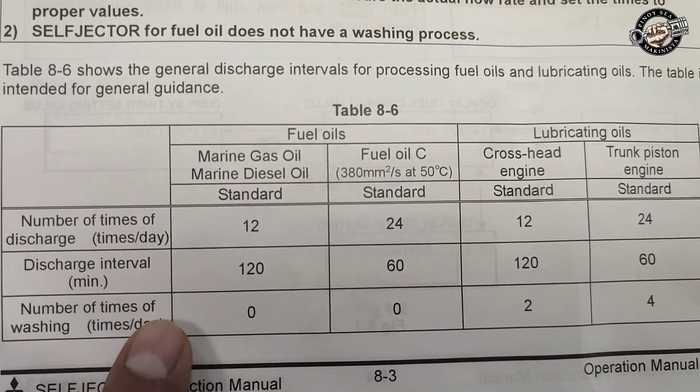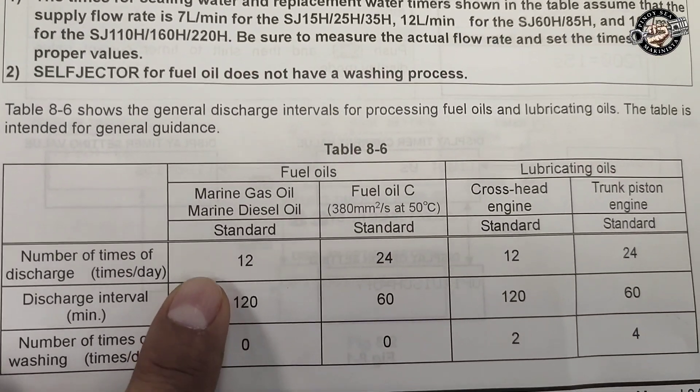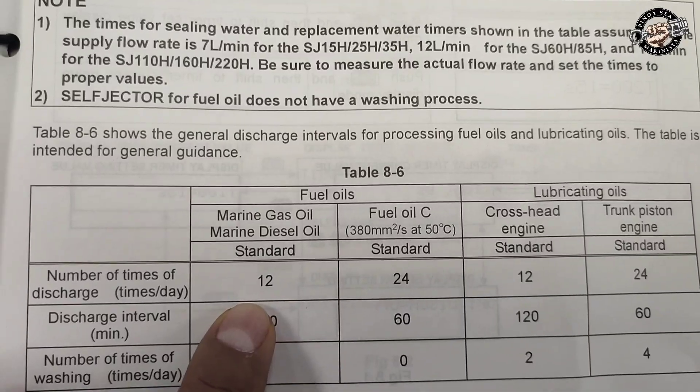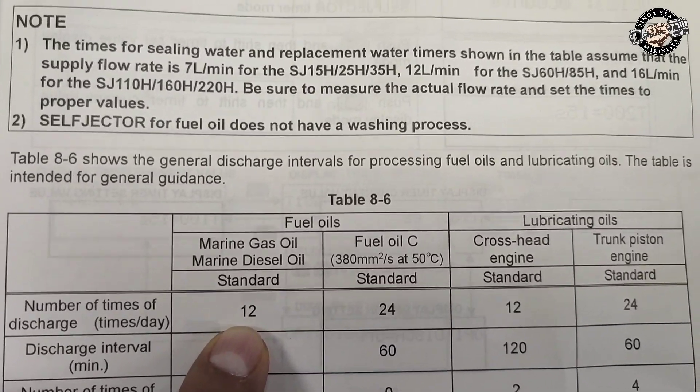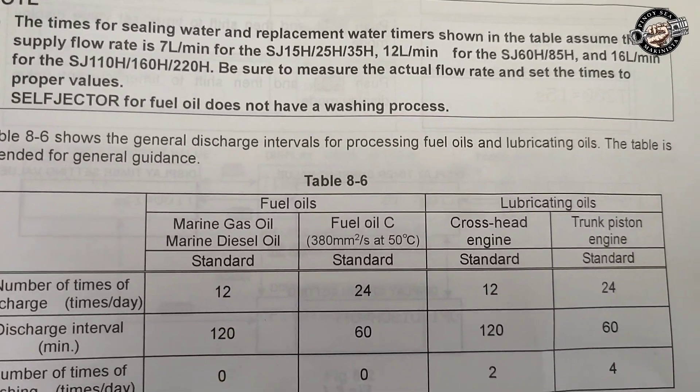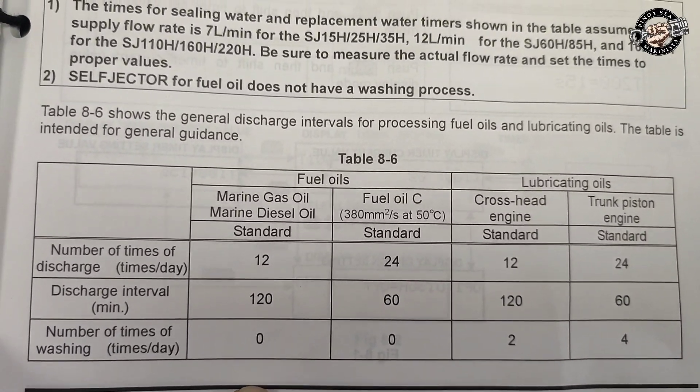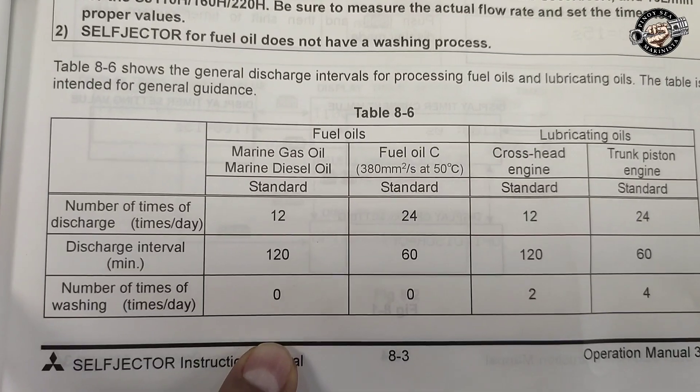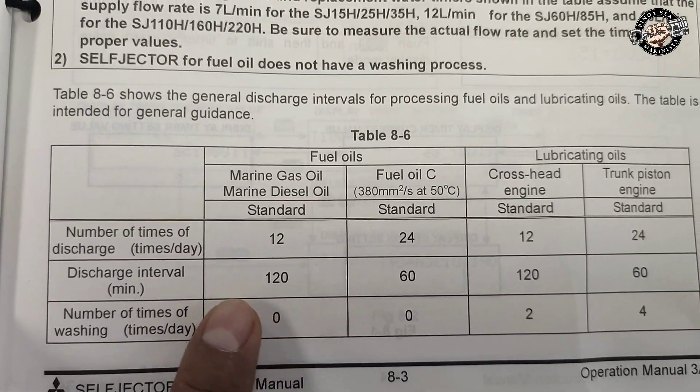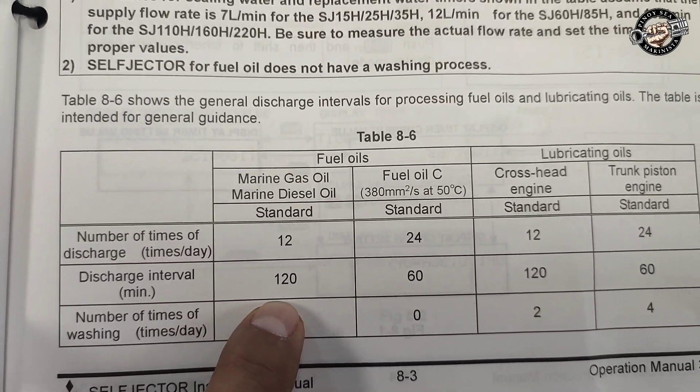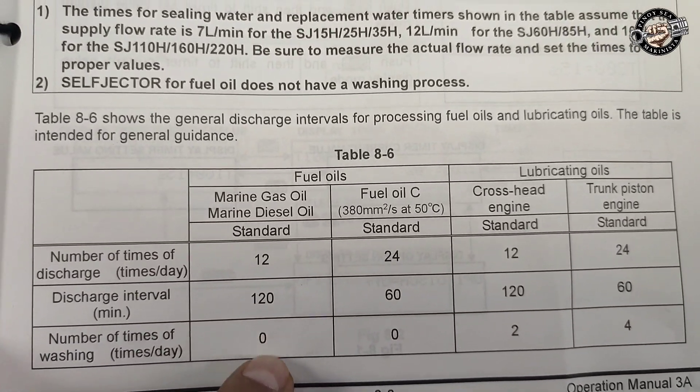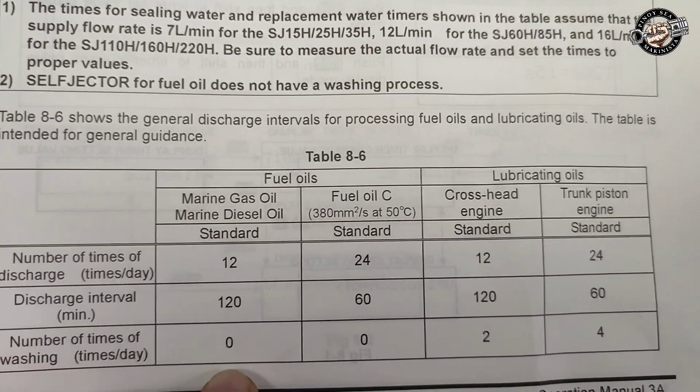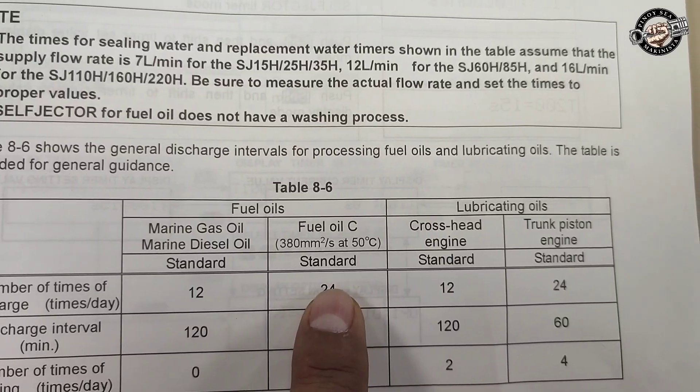For MGO or MDO, the number of times discharge per day is 12 times and the sludge discharge interval is 120 minutes or every two hours.